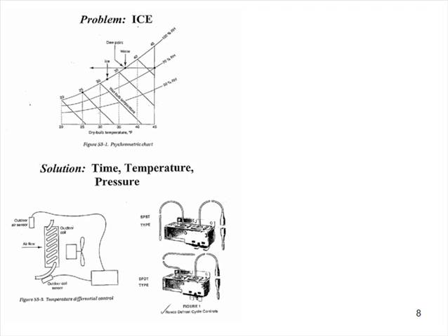And, of course, that's what it looks like when you go into defrost because you get that plume of steam as the hot gas goes out there and starts to melt the ice on a 40-degree night. So those were terrible. The air is very capable of having a lot of moisture at 45 and 50 degrees, and all of it, as it hits that outdoor coil, is going to condense like a son of a gun. In order to sense that this coil has built up with ice, we used one of two methods.